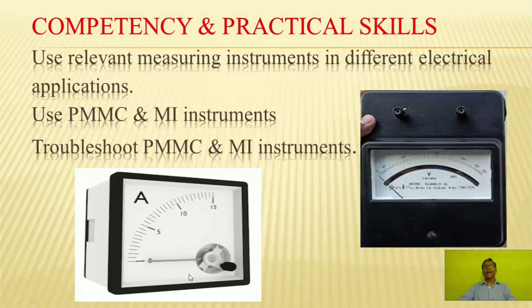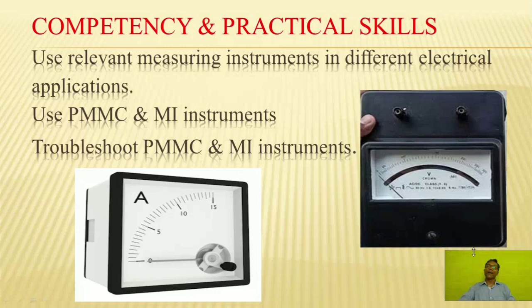You can look at the diagrams. The first diagram is of a PMMC type instrument — it is a PMMC type ammeter with a scale from 0 to 15 ampere. You can see its scale is uniform, and the symbol on it shows that this is a PMMC type meter. The second diagram is an EMI type voltmeter. By looking at the various symbols, you can decide whether this is an AC or DC meter. You can see its scale is non-uniform and initially cramped. PMMC meter scale is uniform, while the EMI type instrument scale is non-uniform.